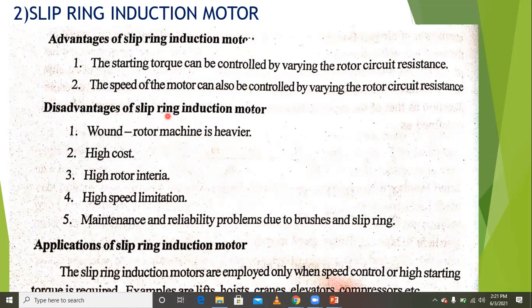The disadvantages of the slip ring induction motor include: the rotor machine is heavier with high cost, high rotor inertia, high speed limitations, and maintenance and reliability problems due to brushes and slip rings.